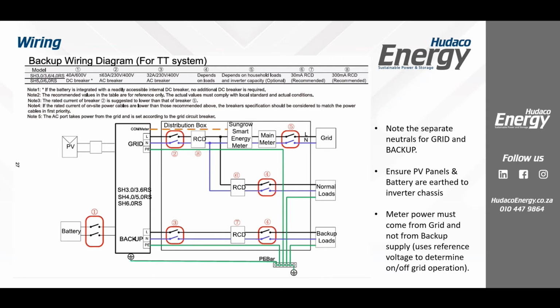Okay. Then coming out of the unit on the backup port, again, as it comes out, we've got the return to DB. So this is a 40 amp breaker. By the way, this can be a 6 mil cable here because we're going to carry no more than about 30 amps. Okay, maybe 32 amps for a short amount of time, but generally a 6 mil cable here is fine with a 40 amp breaker. Here you can use a 10 mil cable. You can use a 63 amp breaker here if you want to.